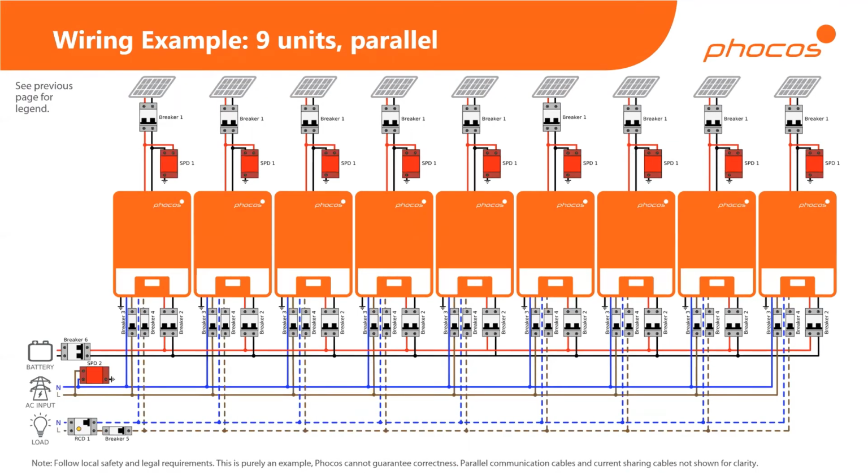Here we have 9 units in parallel. There's also a limitation for a lot of our competition to not have more than 3 units, for example, on a single phase. Like I said before, we can hook up 9 units together, synchronized, and we can literally put them all on a single phase. We're completely free to distribute those units on 3 phases, on a single phase, or in a split phase configuration if you're working with the 120 volt models.